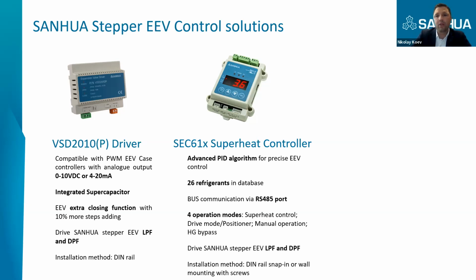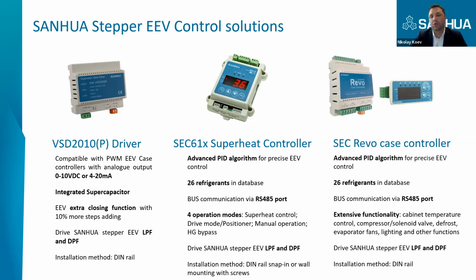And our new flagship controller is called SEC Revo. It is an EEV case controller, which means that besides the superheat control, we are able to control all functions in a cold room or cabinet. Again, this controller comes with an advanced PID algorithm, 26 refrigerants in the database, and the possibility to connect to a monitoring system. I will give you a little more information in the next slides.